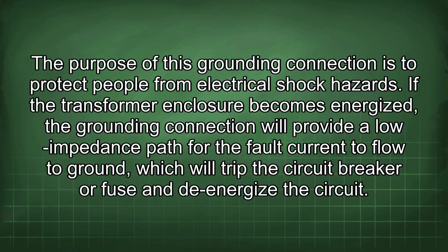The purpose of this grounding connection is to protect people from electrical shock hazards. If the transformer enclosure becomes energized, the grounding connection will provide a low impedance path for the fault current to flow to ground, which will trip the circuit breaker or fuse and de-energize the circuit.